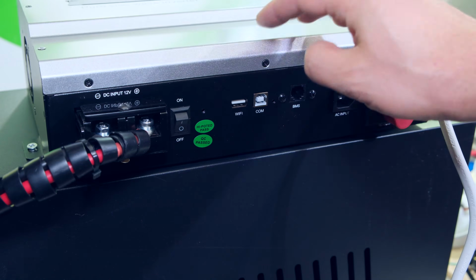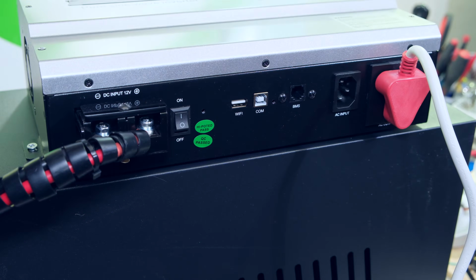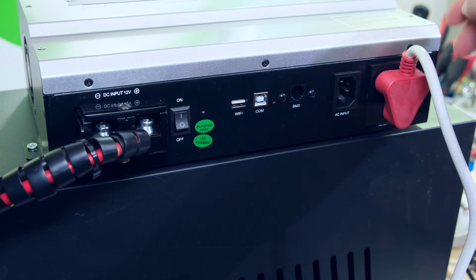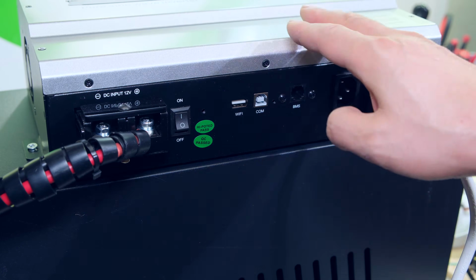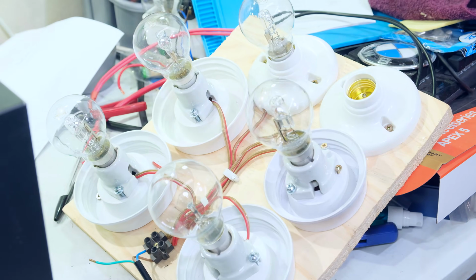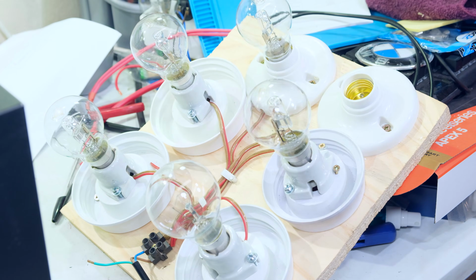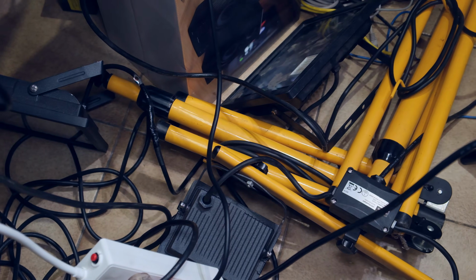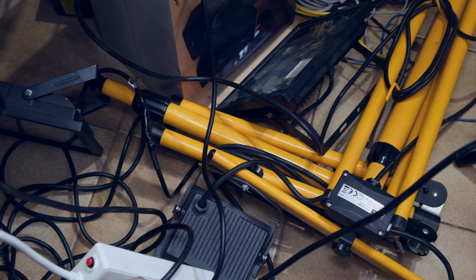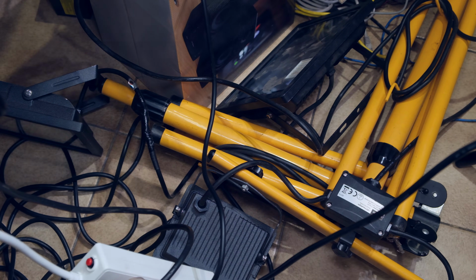Right, so the circuit breaker is in the on position and I can power up the device. I have my load plugged in. There's no input here, so I'm running completely off the batteries. For my load, I've got these light bulbs, each rated at 75 watts. And then I've got some other nonsense on the floor there, a couple of floodlights, 50 watts, 50 watts, 20, 20. And altogether that summates to just over 600 watts.